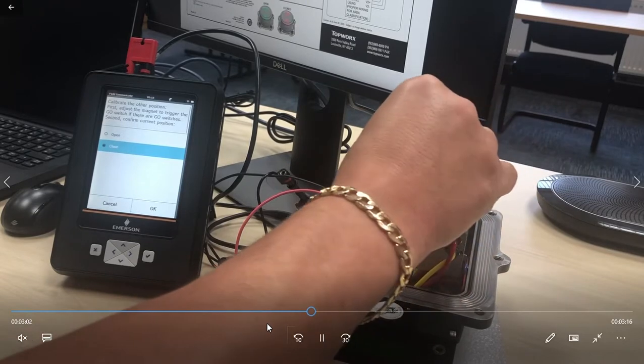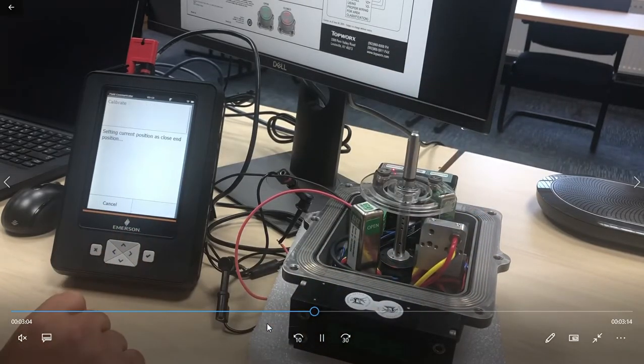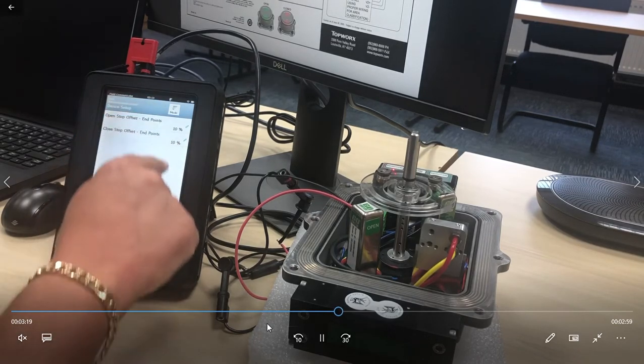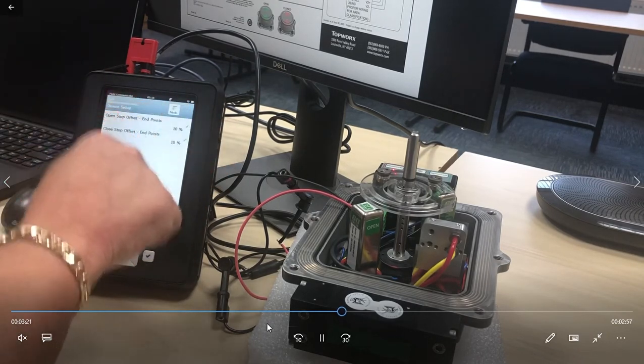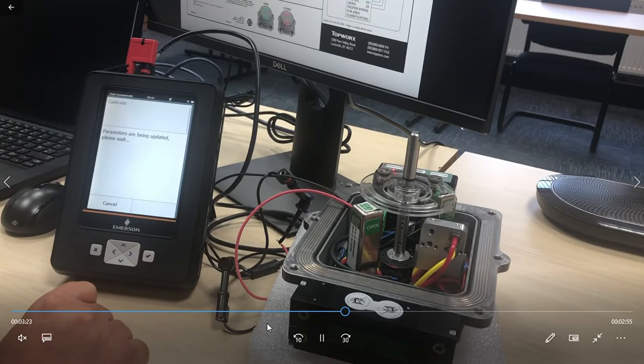We're now connecting to the closed position. So now we're configuring the open and closed position and we're setting that, and as you can see, the calibration is finished successfully. This is the allowable range. This is to calibrate between the open and the end position, so we can have a percentage there where it can be a small percentage out if you need that parameter being set.